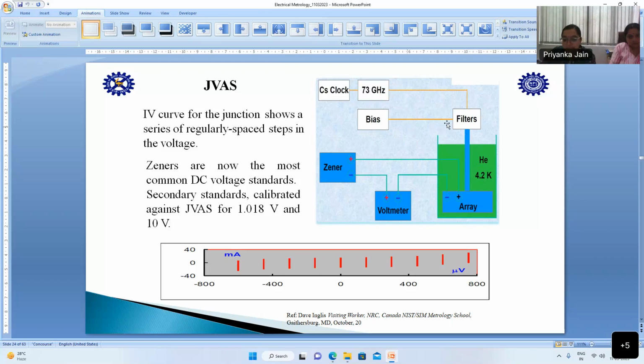So if we apply a bias current to the array and irradiate it with the microwave frequency at this particular temperature, we are generating a voltage which can be measured by a voltmeter and compared with the Zener voltage. This is how Zener is calibrated against JVS. Zener is capable of delivering 1 volt and 10 volt. So in case I am connecting 1 volt of Zener to the voltmeter and I'm generating 1 volt from the Josephson array, we compare both of these voltages and we identify how much is the deviation from the ideal value and what might be the uncertainty of that particular value.